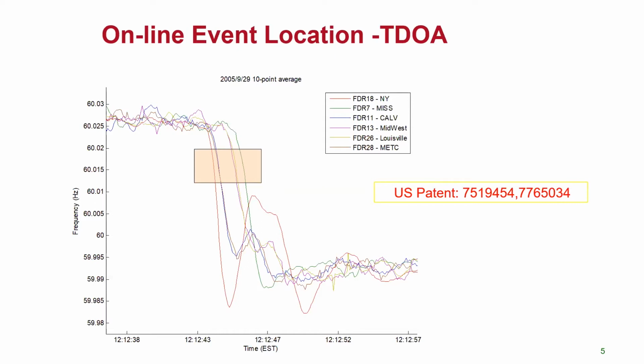Now, one thing we discovered is that because it's a traveling wave, it has time delay. If you look at this particular diagram, I'm looking at frequency and I have them all time-aligned. However, whenever an event happens, I notice there's a delay - one red unit sees the event first, then two others, and so on. So this delay is what I was referring to - the propagation speed of the electromechanical wave.